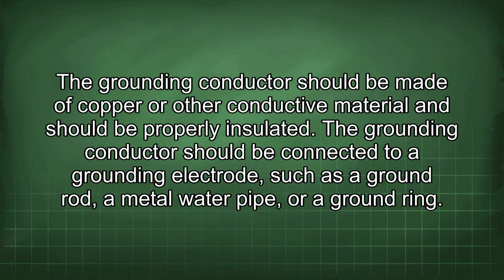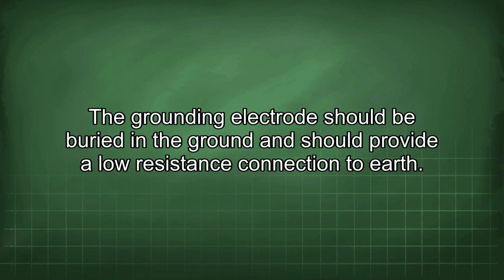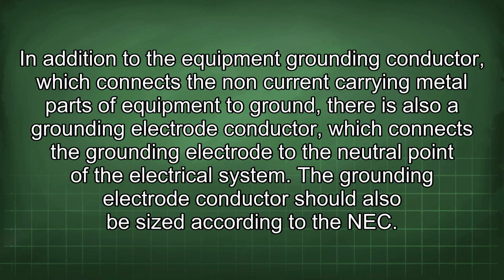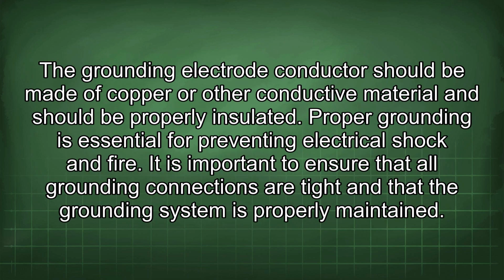The grounding conductor should be connected to a grounding electrode, such as a ground rod, a metal water pipe, or a ground ring. The grounding electrode should be buried in the ground and should provide a low resistance connection to earth. In addition to the equipment grounding conductor, which connects the non-current carrying metal parts of equipment to ground, there is also a grounding electrode conductor, which connects the grounding electrode to the neutral point of the electrical system. The grounding electrode conductor should also be sized according to the NEC. The grounding electrode conductor should be made of copper or other conductive material and should be properly insulated.